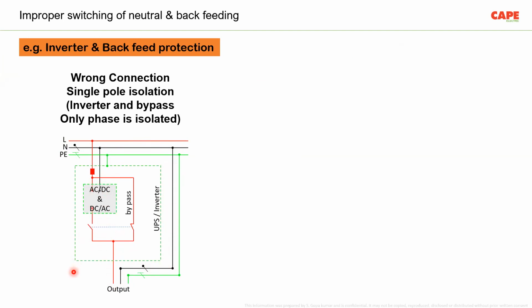With this kind of installation, whenever there is a switch-off condition, whenever there is no power, and once the power is fed from the inverter, there is a high chance of backfeeding. And this backfeeding goes into the line, and your neighbor may get electricity, or somebody working on the high voltage line also gets electricity. As a result, a lot of accidents are happening. A lot of people, especially engineers or technicians working with the distribution companies, are getting electrocuted because of this reason.